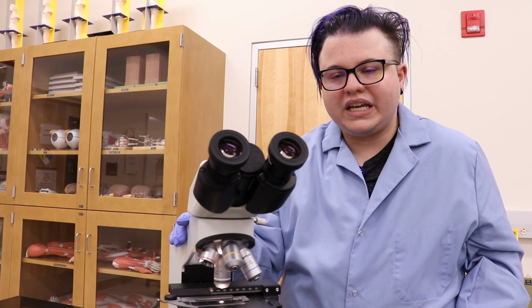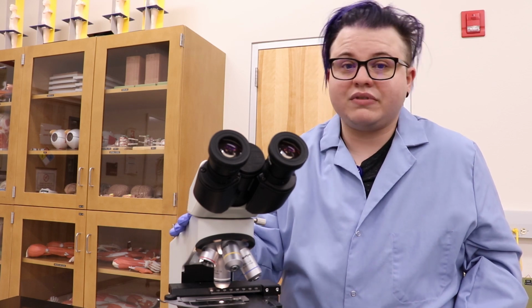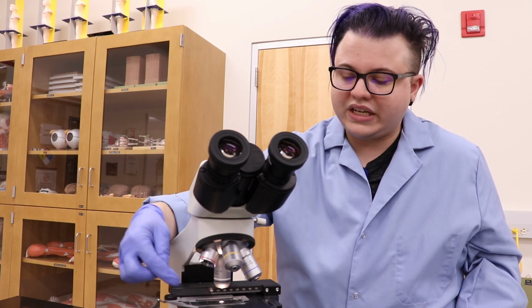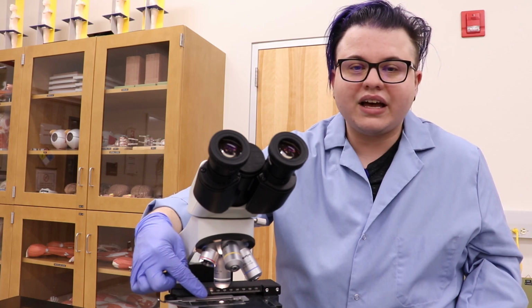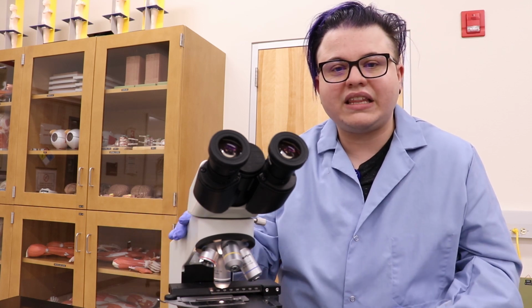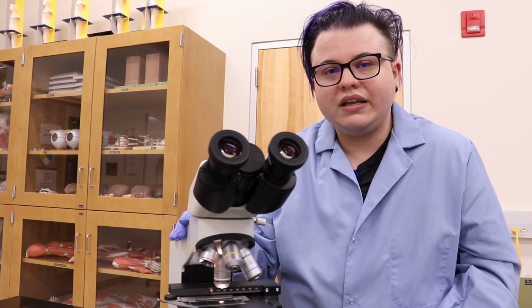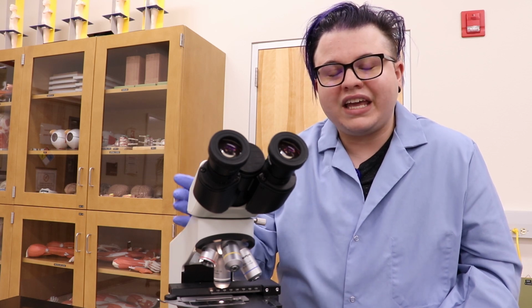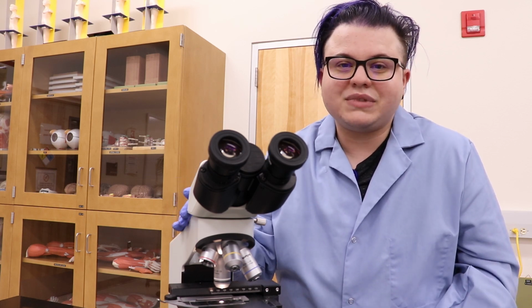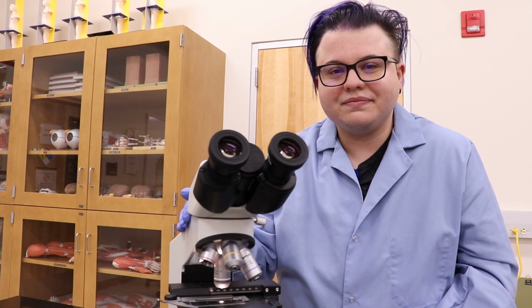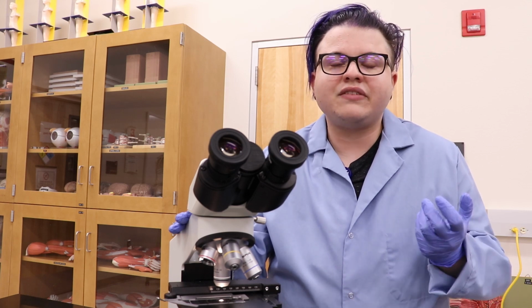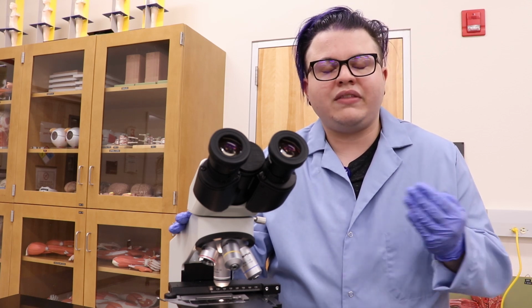Another thing you could try is to make sure that the student's slide is right side up. You can do this by doing a scratch test onto the wax that they use to designate the area that they're preparing their smear. If it doesn't leave back a divot, you know that their slide is upside down, and it needs to be turned right side up. The last thing you will want to try is to actually clean the objective quickly to see if the objective itself was dirty rather than any of the other options.